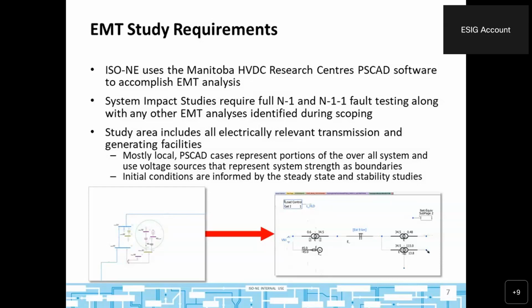Case setup normally starts by converting the ISO New England developed stability case, originally used as part of the SIS for stability testing in PSSE, into a PSCAD case using ETRAN. We then add information not originally included in the stability case, like transformer saturation, frequency dependency of lines if needed, and manufacturer-specific models, since these aren't generic EMT models.